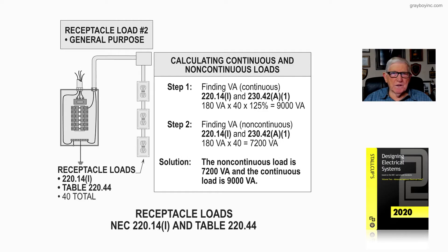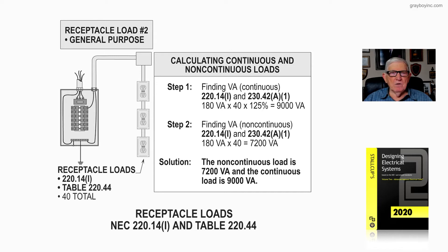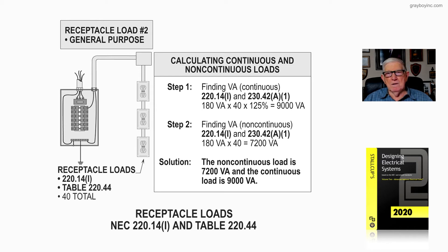Now let's look at figure 23-9, and we're going to figure the receptacle load, which is the second load we want to be looking at. We're looking at general purpose receptacles, which means they're operating less than three hours — this particular load. Notice the receptacle load is NEC 220.14(I), table 220.44, and we have 40 total. The table gives you a demand factor so that you can have less load on them because they're non-continuous use.